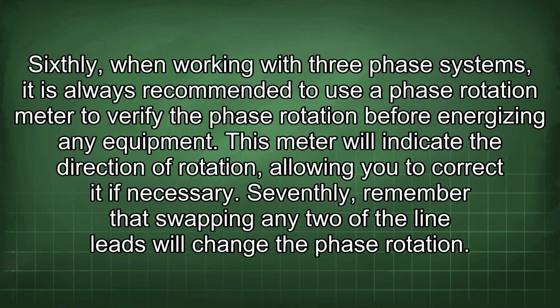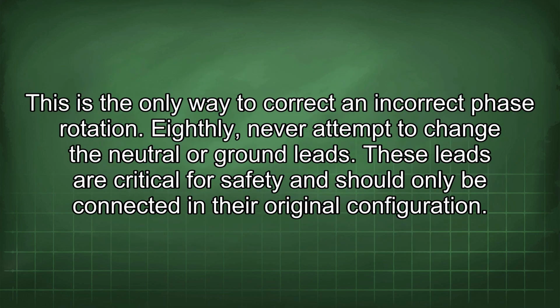Sixthly, when working with three-phase systems, it is always recommended to use a phase rotation meter to verify the phase rotation before energizing any equipment. This meter will indicate the direction of rotation, allowing you to correct it if necessary. Seventhly, remember that swapping any two of the line leads will change the phase rotation. This is the only way to correct an incorrect phase rotation.